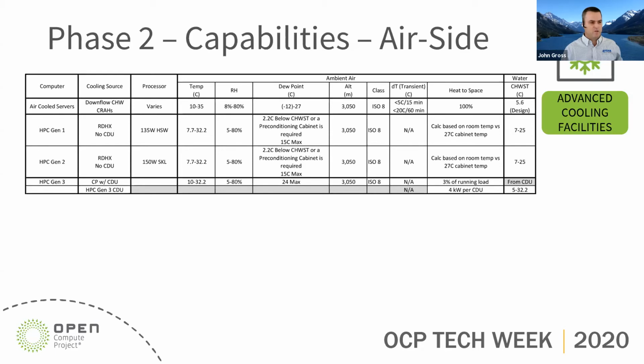The other thing that came into play is that the solution we were getting from the ITE manufacturer was from the CDU and its distribution piping all the way to the ITE. So it was a turnkey system. And in their operational setup, the TCS loop piping was not going to be insulated. As a result, we were going to have heat gain into the air in the data hall from the TCS uninsulated piping, which was going to cause an airside load that we hadn't initially anticipated.